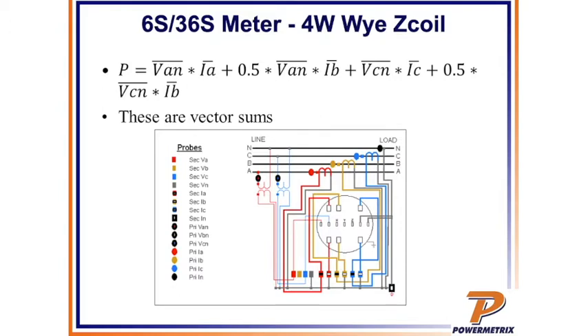So what we're going to do is John now is going to do an example, running the test on a 6S meter. And notice that on a 6S meter, I've got two potentials, but three currents. Obviously this is a non-Blondel compliant service. So we have to make the assumption of the B voltage because we have to half the current for A and C. And you're going to notice that the vector diagram is going to look really bizarre when we start to run the test. Okay. Take it over to John.